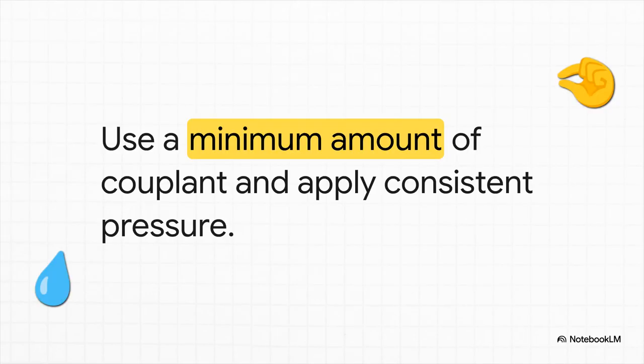But accuracy isn't just digital. It's highly physical. Between the transducer, which is the probe you're physically holding, and the metal itself, you have to use a couplant. Usually this is a specialized gel, and it's kind of an art form. You must use a minimum amount and apply perfectly consistent pressure. Because think about it, if you're pressing really hard on one reading and too lightly on the next, you're actually changing the thickness of that gel layer, and that right there introduces errors into your highly sensitive micromeasurements.